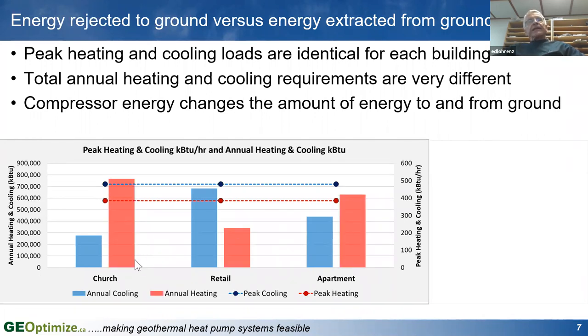The heating loads, on the other hand, are, in this case, exactly the opposite. A church, for example, is sitting empty much of the week. And because you're not getting heat gain from people in the church, from lights in the church and those kinds of things, less activity in there, a lot more of the heat has to be taken from the ground than in a retail store. In a retail store, for example, the lights and the people provide a lot of the heat for the space that doesn't need to be coming from the ground.